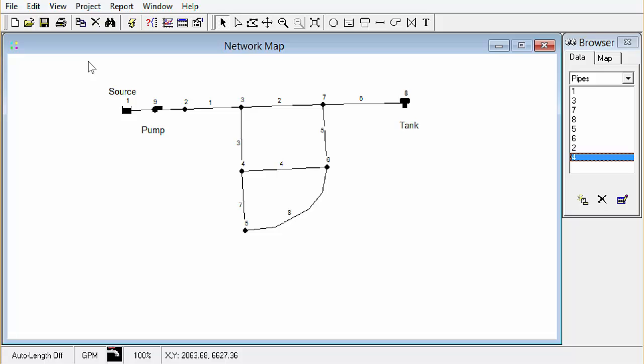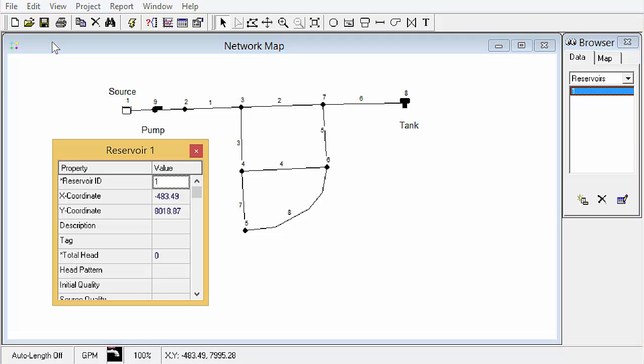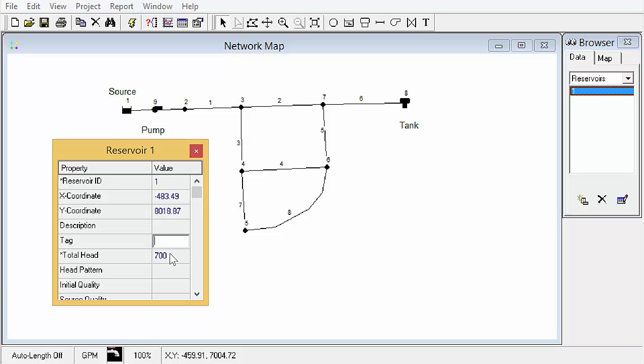I'm going to refer to page 14 in the user's guide for the table of values for nodes and links. We'll just start in link 1 and we can access the information in several different ways. We can double click on an element. This brings up this little editor and the data we're changing here is the elevation which is actually total head for a reservoir. So we're going to give that a 700. So this reservoir is a fixed boundary condition. So this if unless we give it a head pattern it will always be a boundary condition at 700 and then the units of length. In our case we're using feet.